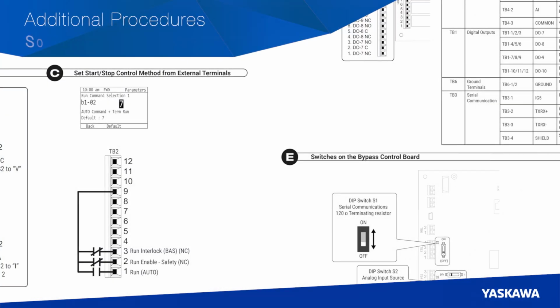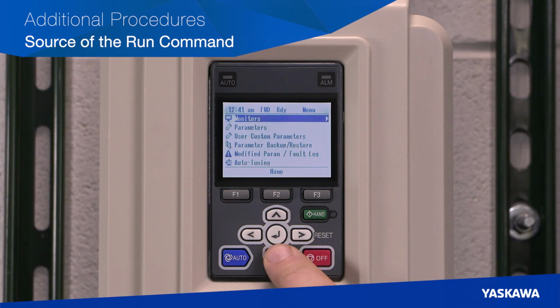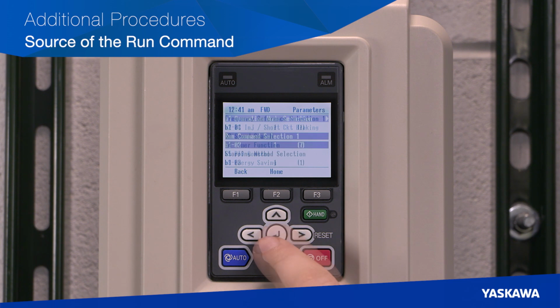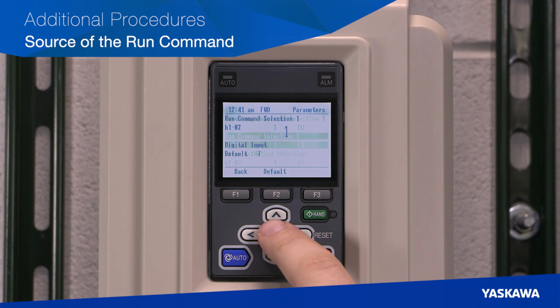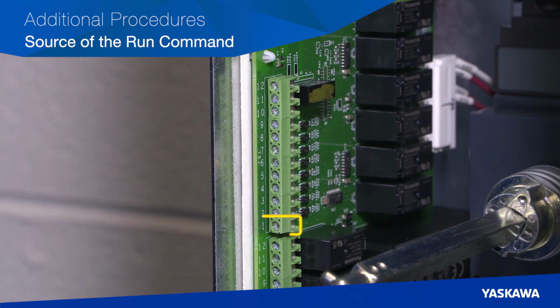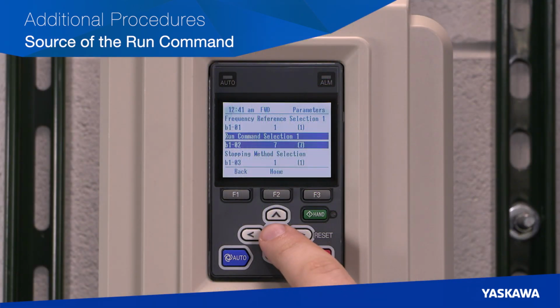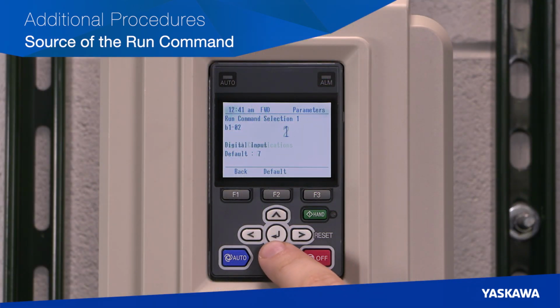Additional procedure C is for setting the source of the run command. Navigate to parameter b1-02, where the run command selection 1 parameter can be changed if needed. For an external input and an auto command from the keypad, select 7 for the run command. Connect run command signal wiring between terminals TB2-1 and 9. Select a setting of 0 if you wish to have a run command via the keypad only.